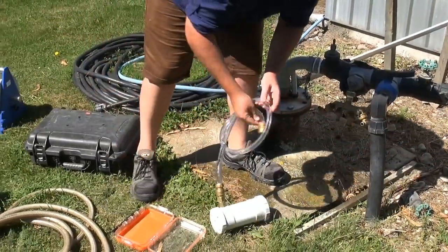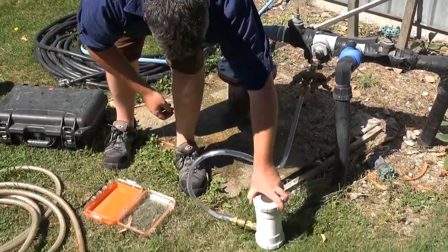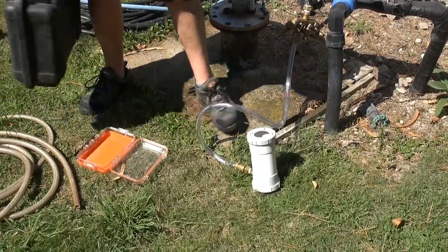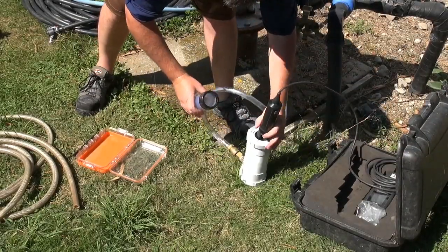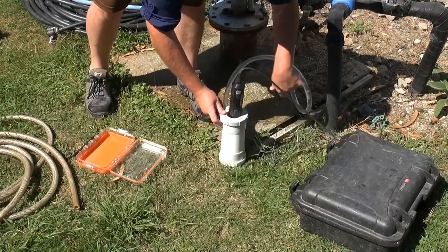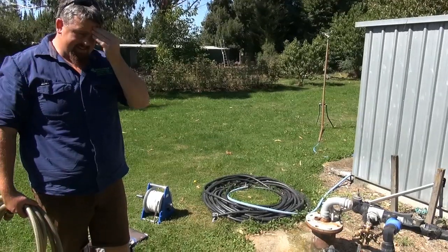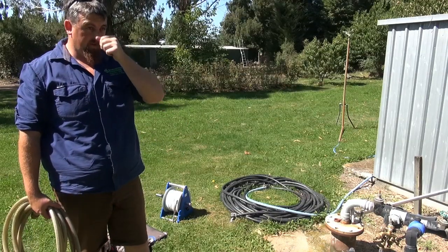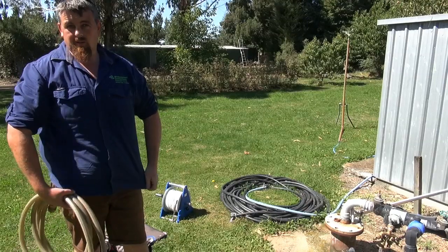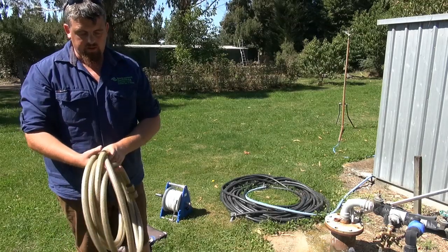The flow cells you can buy from manufacturers if you wish or you can build one. As long as the water comes in the bottom and flows out the top, that will be sufficient. For the meter you can use a pH 4 and 7 buffer. I don't do a 10 because the pH of waters I go to generally don't go above about 7, so a two-point reference is more accurate than a three. If you're doing coastal environments it might be different — it really depends on the water.